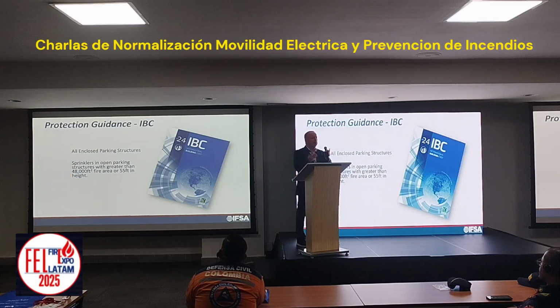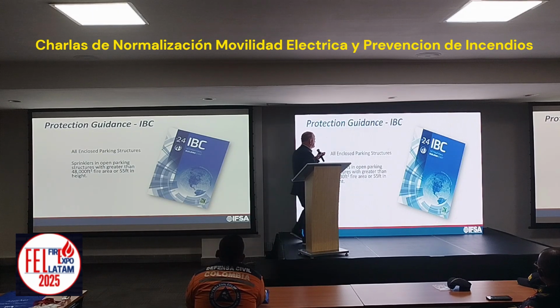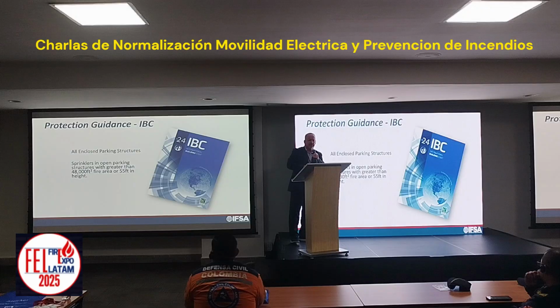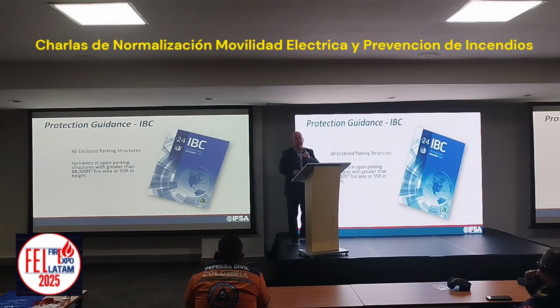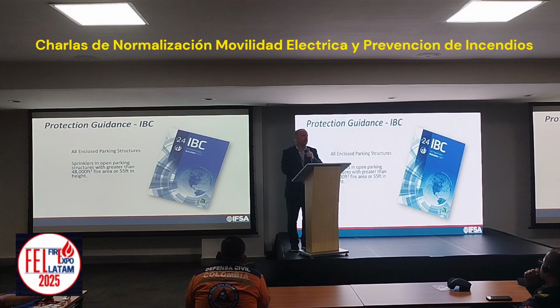Now, when it comes to the protection scheme for parking structures, the International Building Code, 2024 edition, says everything that's an enclosed parking structure needs to have fire sprinklers designed into them. Sprinklers in open parking structures is limited to very small areas. But even so, that's a challenge in and of itself.